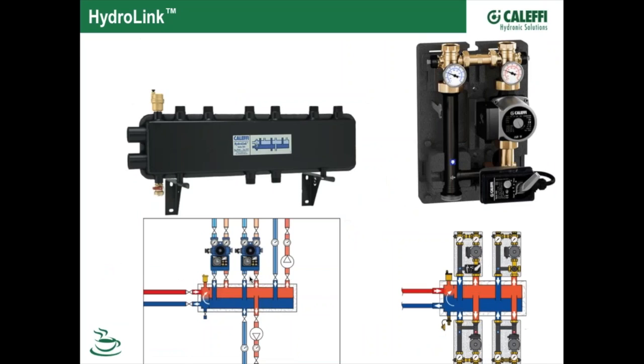This is probably one of my all-time favorite products, what we call the HydroLink. What we did here is we've taken the hydro separator function and we've evolved it to where we can have the hydraulic separation in the end chamber here. There's our two pipes coming from our heat source. Hydraulic separation here, closely spaced T's if you think of it that way. But also let's put the distribution piping in the same box. So now all we do is make our connection to the boiler, our heat source here, heat pump, whatever it might be. And now we've got our zone pumping that can go right onto that.